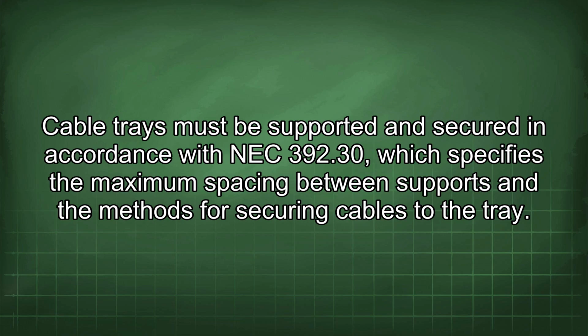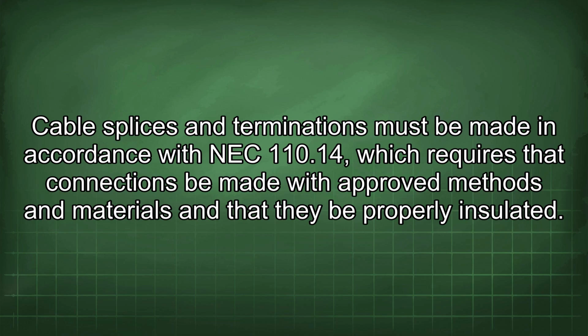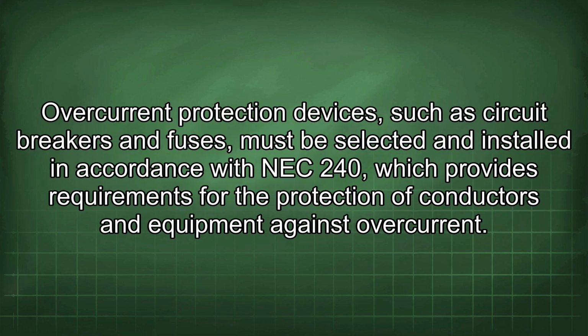Cable trays must be supported and secured in accordance with NEC 392.30, which specifies the maximum spacing between supports and the methods for securing cables to the tray. Cable splices and terminations must be made in accordance with NEC 110.14, which requires that connections be made with approved methods and materials and that they be properly insulated. Overcurrent protection devices, such as circuit breakers and fuses, must be selected and installed in accordance with NEC 240, which provides requirements for the protection of conductors and equipment against overcurrent.